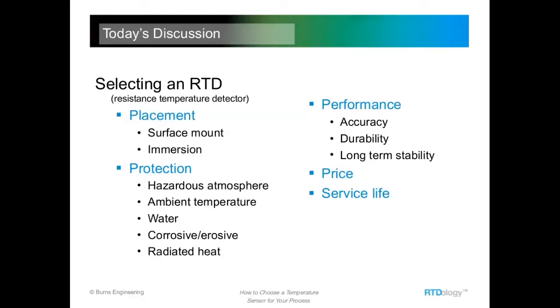So today we're going to go through just a made-up process where we're heating water. We're going to talk about whether we should select an RTD or a thermocouple for this process, where it should go in the process to get the best measurement, and look at how to protect it, both inside the piping and outside. We'll talk about performance of the sensor, and finally we'll wrap up with the price and the ongoing maintenance, and what you can expect for a lifetime out of a sensor in that type of application. So those are the takeaways from today's presentation: whether you want to choose a surface mount or an immersion style sensor, how do we protect it, what kind of performance can you expect, and what do we do to maintain it over its lifetime.